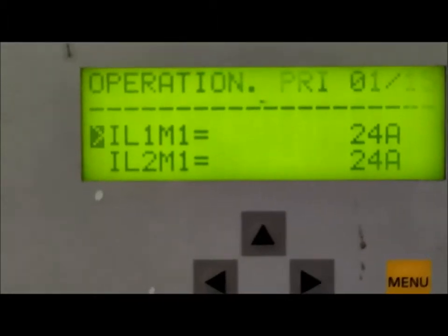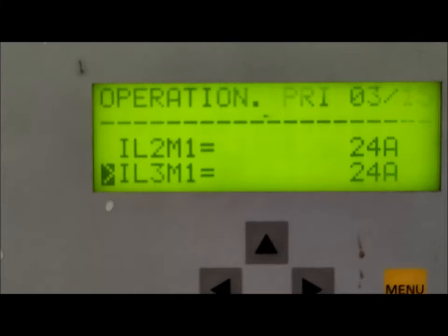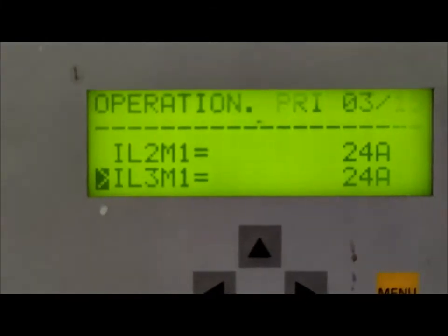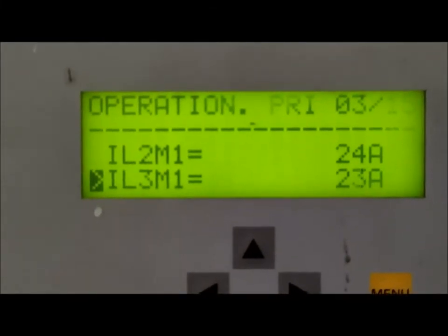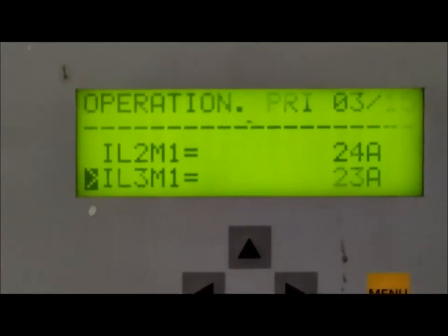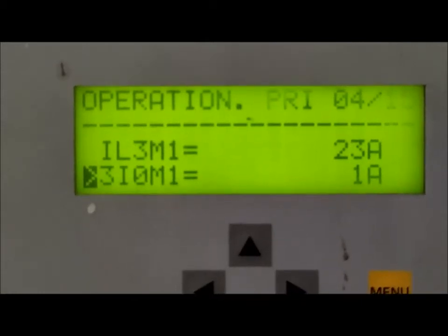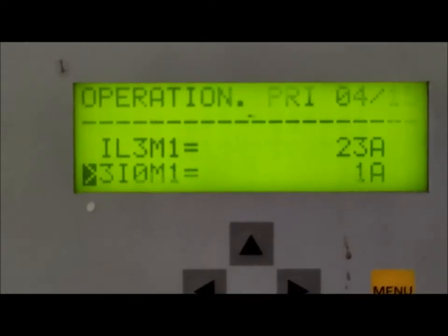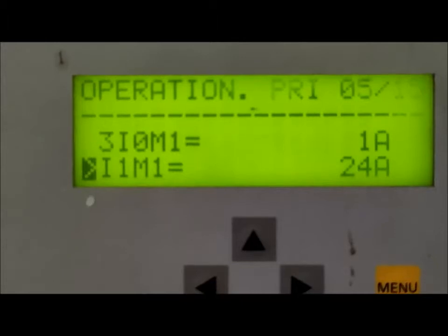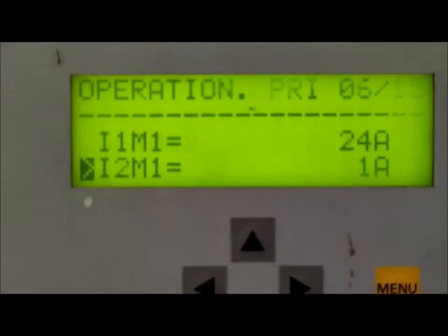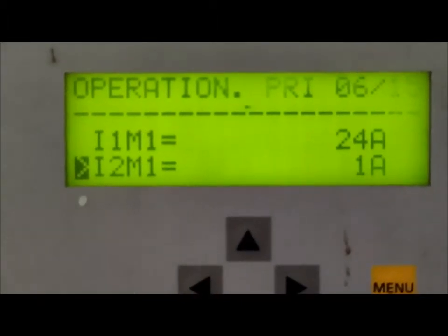Here IL1, IL2, and IL3 M1 are the HV side currents. All are 24 amperes and C phase is 23 amperes. 3I0 is the zero sequence current, I1M1 is the positive sequence current, and I2 is the negative sequence current.